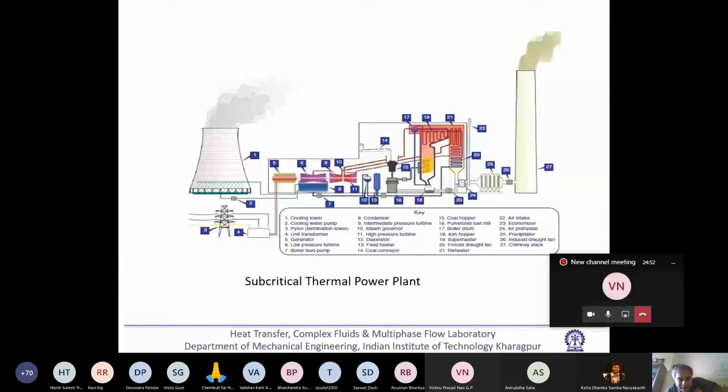And then hot air is going through this pulverizer. Then coal also has a lot of moisture. You know that a large amount of coal will be needed. In open space, the coal will be dumped. It will collect all the moisture, rainwater will fall on it. So the hot air, that's why air preheating is needed, will take away those moistures. So that combustion will become very efficient. We want to get the full worth of the money we are spending for our fuel, that is coal. So that's why air preheating is needed.